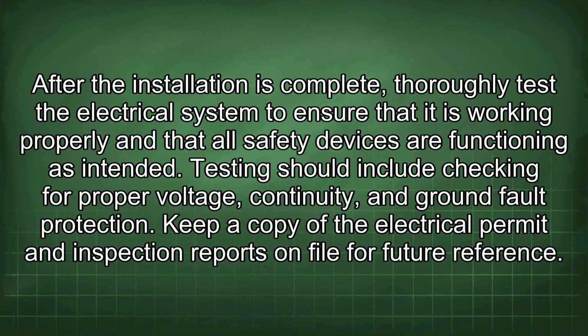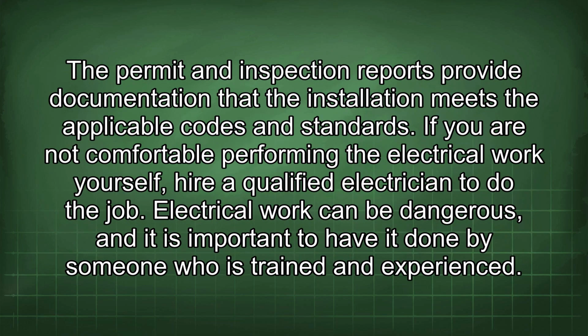After the installation is complete, thoroughly test the electrical system to ensure that it is working properly and that all safety devices are functioning as intended. Testing should include checking for proper voltage, continuity, and ground fault protection. Keep a copy of the electrical permit and inspection reports on file for future reference. The permit and inspection reports provide documentation that the installation meets the applicable codes and standards.